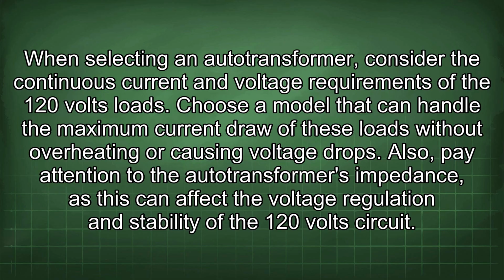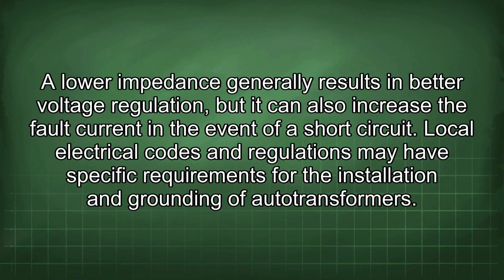When selecting an autotransformer, consider the continuous current and voltage requirements of the 120 volt loads. Choose a model that can handle the maximum current draw of these loads without overheating or causing voltage drops. Also, pay attention to the autotransformer's impedance, as this could affect the voltage regulation and stability of the 120 volt circuit. A lower impedance generally results in better voltage regulation, but it can also increase the fault current in the event of a short circuit.